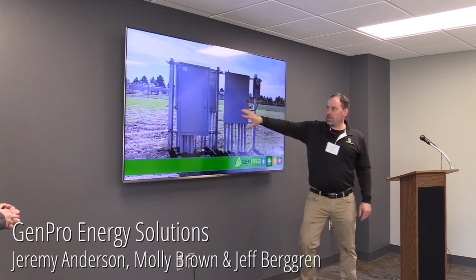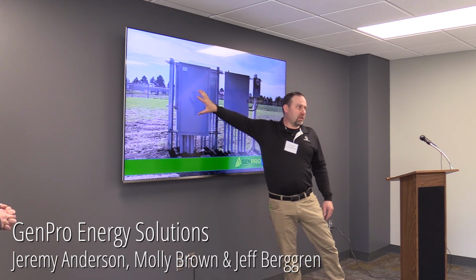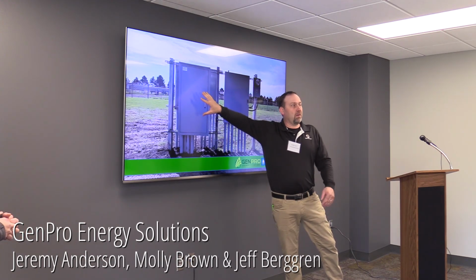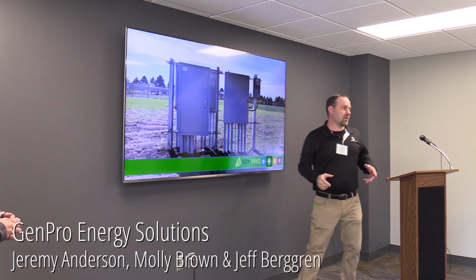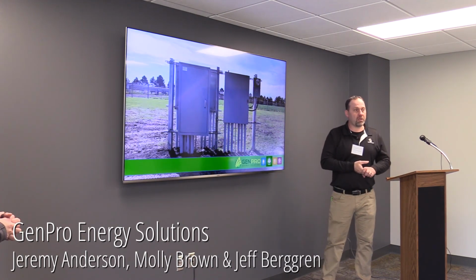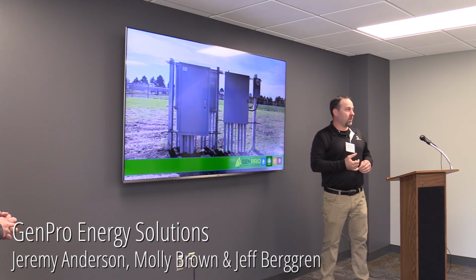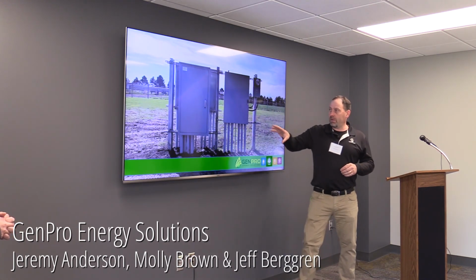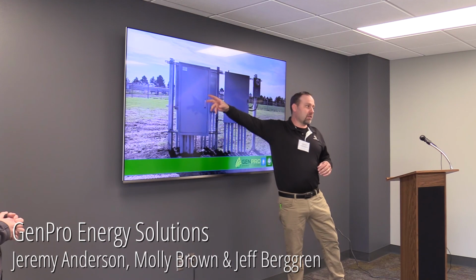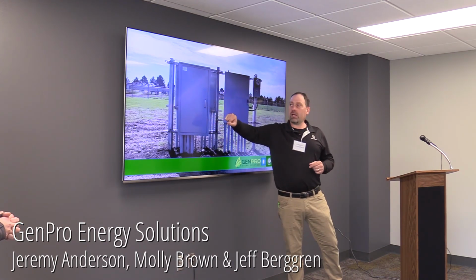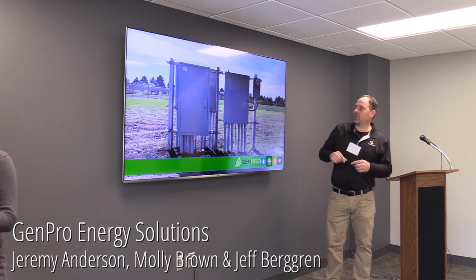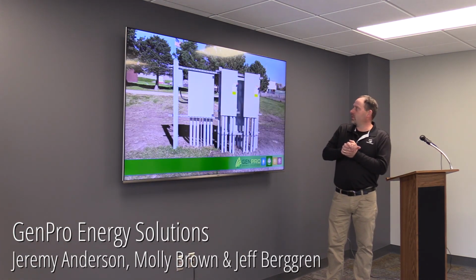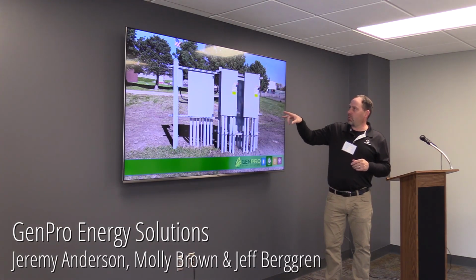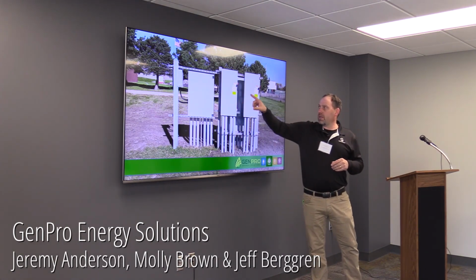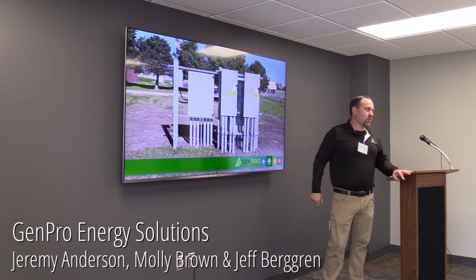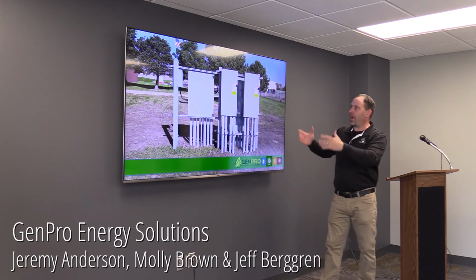We come out of the CT box and we feed this box, which is called a disconnect SEL relay box that NPPD requires us to put in. In short, it is another layer of protection for them so that there's no backfeed on their line. Now, we built a disconnect into this SEL relay box, so there's a way to shut off the whole system right in this box. On the backside, do you have a picture of the backside? Probably not. Oh yeah, thank you. So that's the other side, and we have two inverter stations at Aurora, and one disconnect controls one inverter station, one disconnect controls the other, and this is the complete power setup for Aurora.